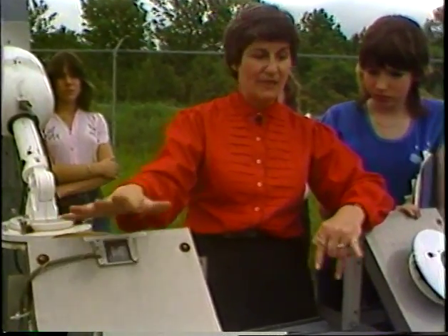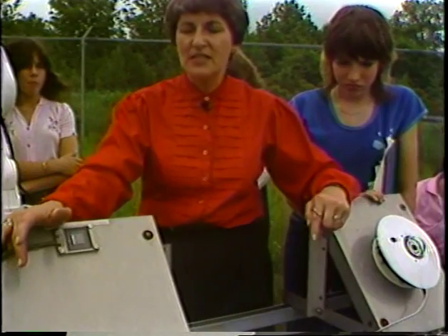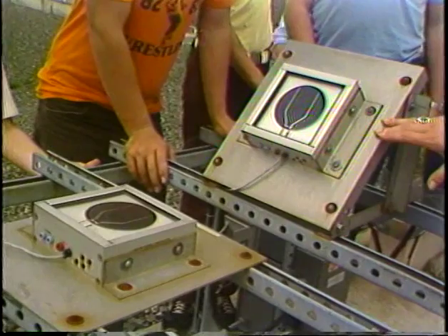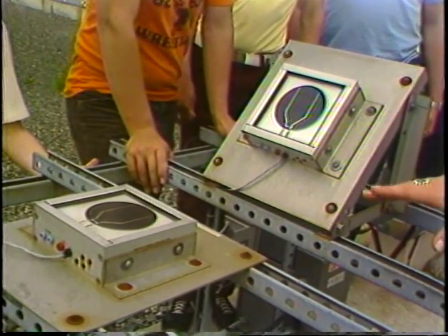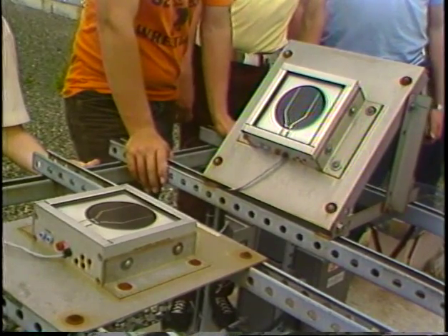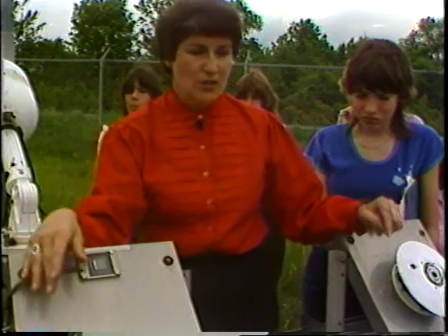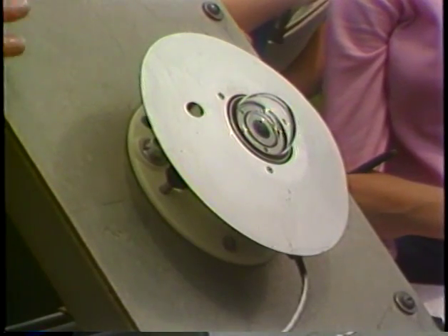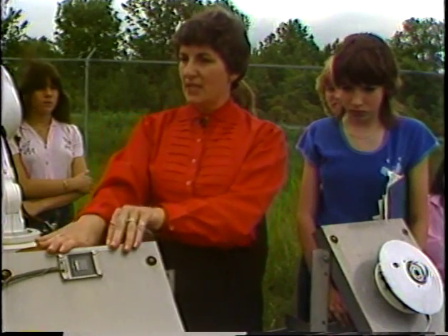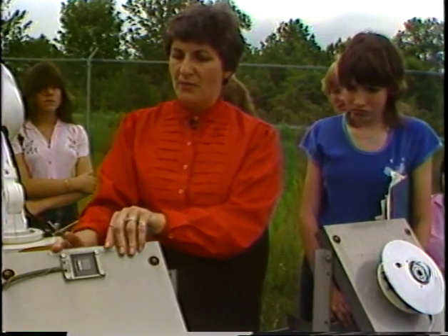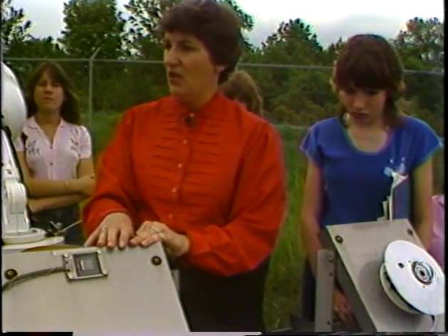These would be the last 7 lines on the computer screen that we saw, because all of these instruments measure insolation. So we have a reference cell on the array plane, which is a 50-degree angle to correspond with all of our subarrays, and a reference cell on the horizontal. Correspondingly, we have a pyranometer, which is on the array and also on the horizontal. And this one that you see here is the United States Government Department of Energy reference cell, which is a sample cell, which is also being tested on this site.